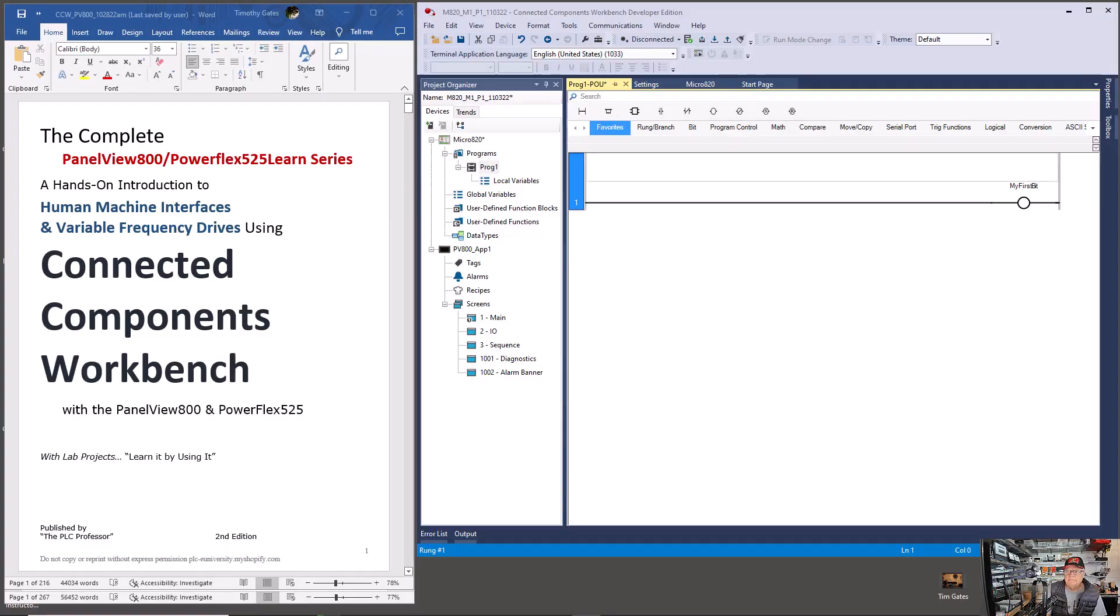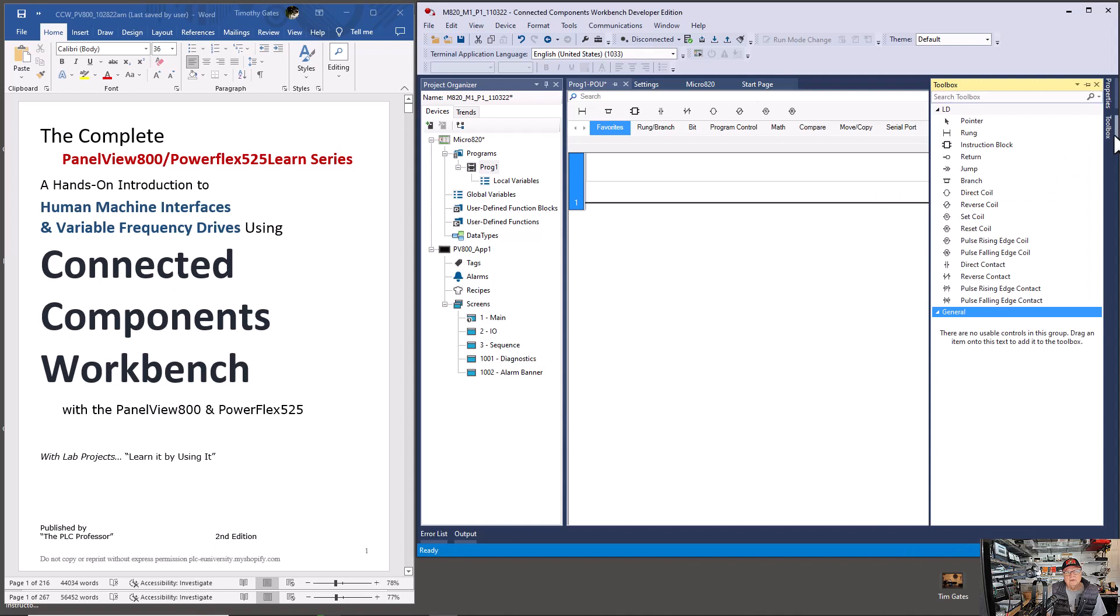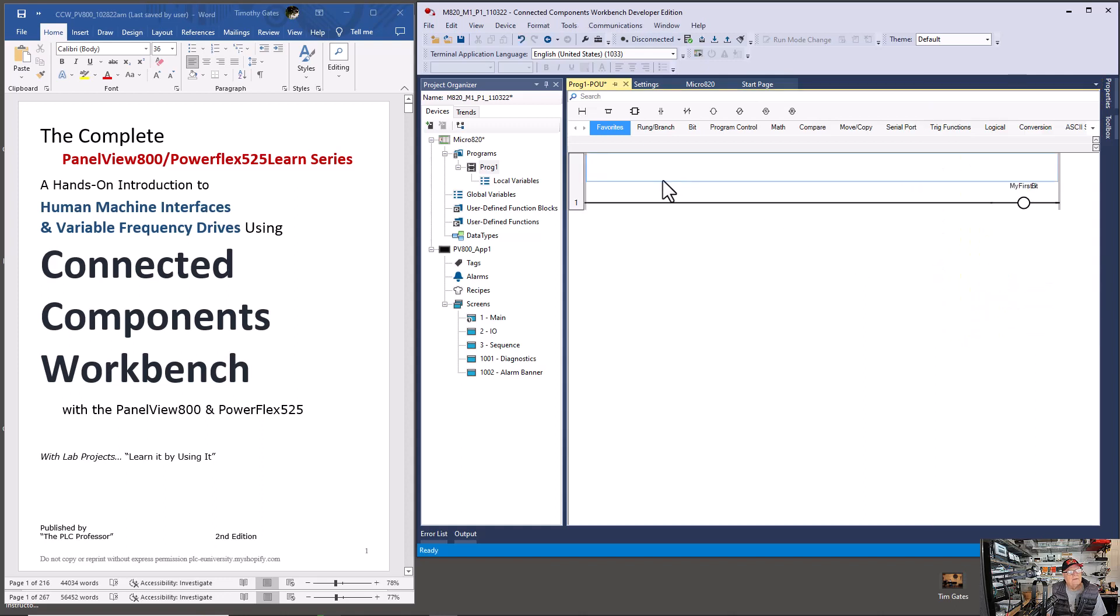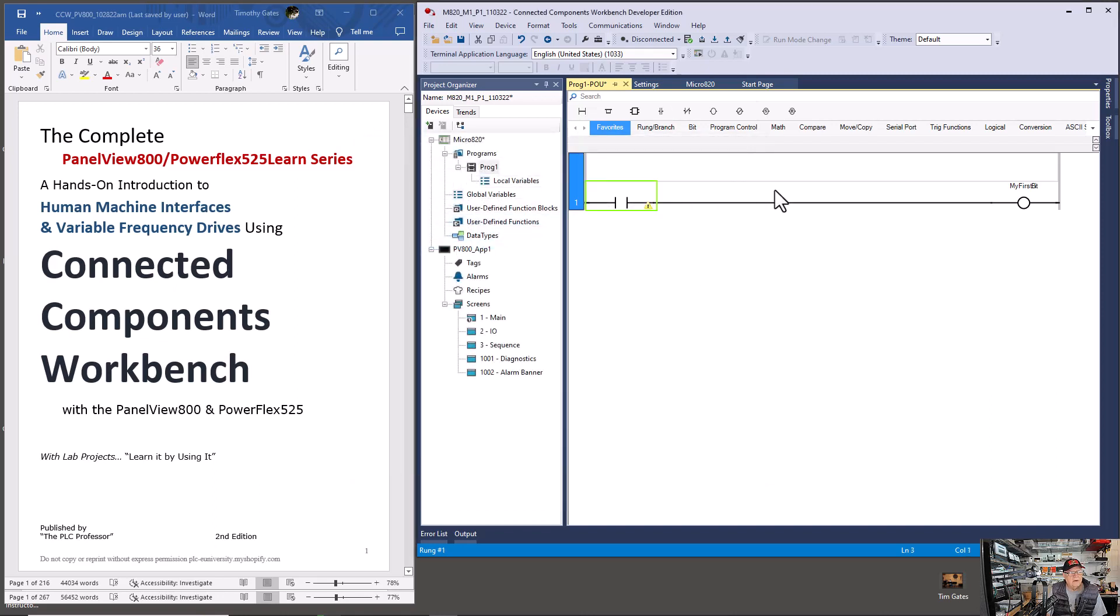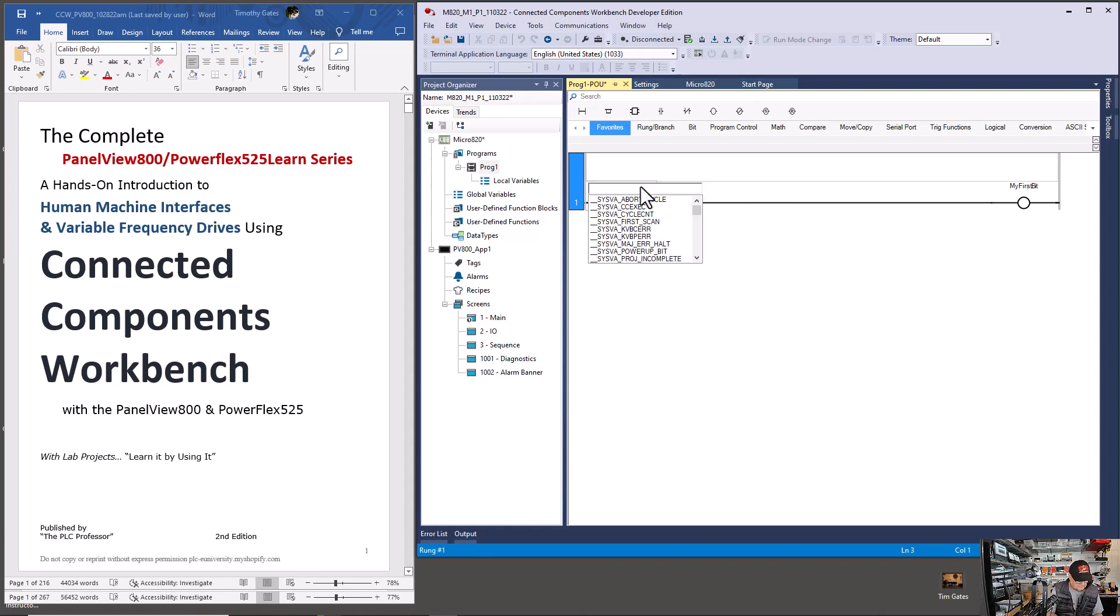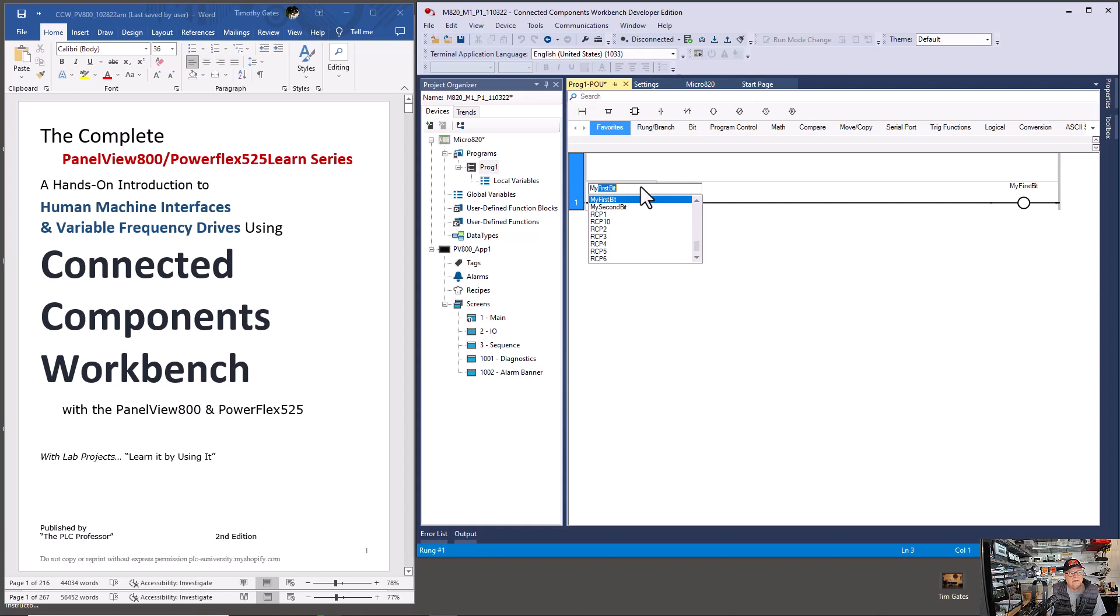We had you disconnect. In other words, go offline. And now we're going to add another instruction to our logic. Several ways you can do that. You can go to toolbox and you can go to direct contact. Or now that they've improved the menu you can go up here and just drag down a true if on. This instruction is true if the bit that it addresses in memory is on. Now I realize that they call it a direct contact or I think an XIC. I don't call it that. And this was my second bit. Now we already added these tags or these variables. You see the type forward, it comes up MY and then it shows my first bit. Right below it is my second bit. Pick that and voila, there it is.